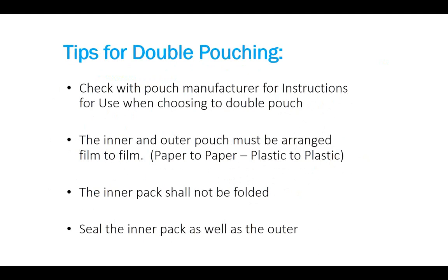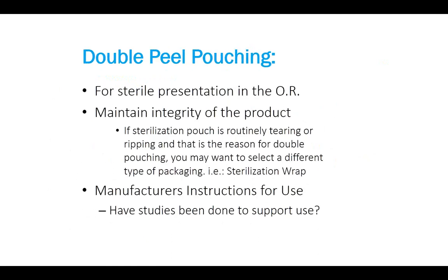The inner and outer pouch must be arranged film to film, paper to paper. The inner pouch should not be folded. It needs to be sealed. Seal the inner packet as well as the outer one. Again, follow the OEM IFU for double pouching. That's very, very important. Most people double pouch for sterile presentation in the OR. I get asked this a lot. Or they do it because we've always been doing it, and the old pouch was a bad pouch and it leaked at the seal, and they might have changed pouches since then.